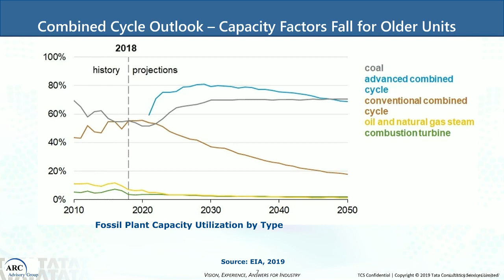So what is the impact of this on the operation and maintenance of these plants? And that really takes us to my second point, that the reduced capacity utilization will bring some major changes to operation. Let's look at that now. For operations, plants are going to see much different operating modes than they are accustomed to. First of all, we'll see more partial load operation, which is very challenging for coal plants and less efficient generally for gas-fired combined cycle units. We'll see more cyclic operations.